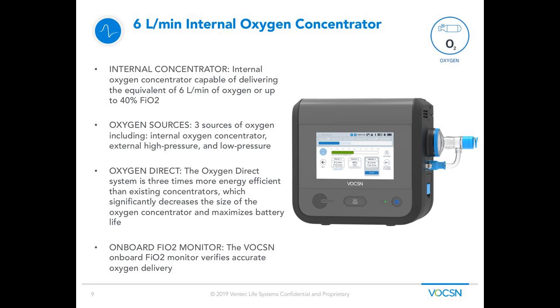This next slide talks about VOCSN's internal oxygen concentrator. The internal concentrator is capable of delivering anywhere between 0.5 and up to 6 liters of O2 flow equivalent, which is about 40% FiO2 for the average adult male. In addition to the internal concentrator, VOCSN is also able to provide oxygen from an external high-pressure source or an external low-pressure source — three ways of delivering oxygen to your patients. VOCSN delivers oxygen through the oxygen direct system, which allows it to run three times more energy efficient than traditional concentrators. VOCSN also has onboard FiO2 monitoring to accurately monitor patients' oxygen delivery.